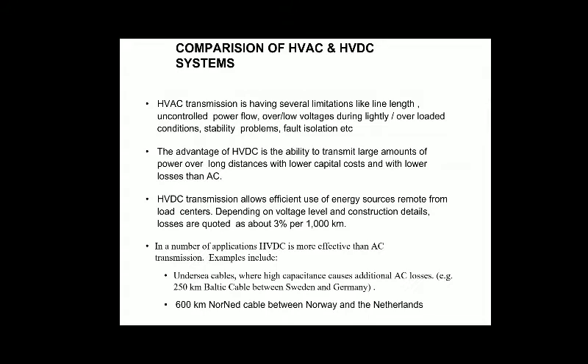Examples include undersea cables, where high capacitance causes additional AC losses. The AC transmission system has inductance and capacitance in the wire carrying the current, but DC conductors are free from these. For example, the 250 km Baltic cable between Sweden and Germany, and the 600 km NorNed cable between Norway and the Netherlands use HVDC. HVDC also enables long-distance power transmission without intermediate substations, for example in remote areas.